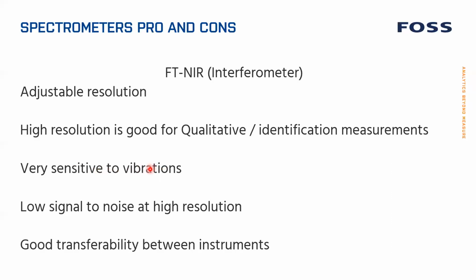Because of the moving mirror, it's very sensitive to vibrations. And if you use the high resolution, you get a very low signal to noise, which means that if you want to use it with high resolution for qualitative measurements, it's really bad for quantitative. So you can't use it for both at the same time, because that doesn't work well. They do have good transferability between instruments.